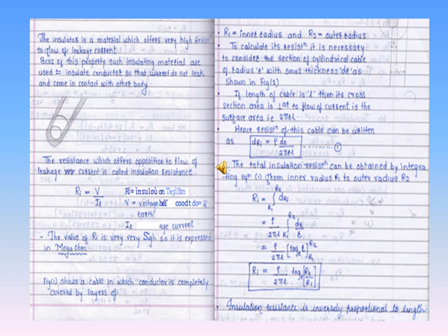The resistance of insulating materials decreases with increase in temperature — they have a negative temperature coefficient. Moisture content also affects insulation resistance: if moisture increases, the value of Ri decreases. From the derivation, the final formula for Ri = ρ / (2πL) × log(R2/R1), where R1 is the radius of the conductor and R2 is the radius of the conductor plus the insulation thickness. An important point: insulation resistance is inversely proportional to length, while conductor resistance is directly proportional to length.